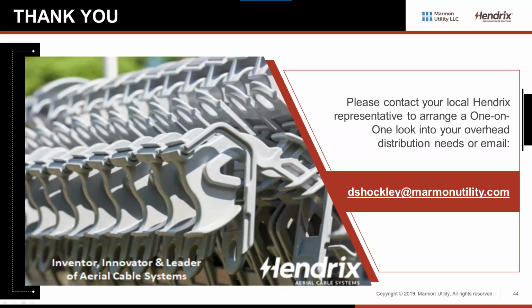But the standard is our 14-inch bracket for 15 kV systems and our 24-inch bracket for 25 all the way up to, I think I said 35 kV, but that's actually good all the way up to 46 kV.